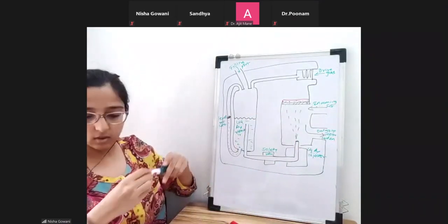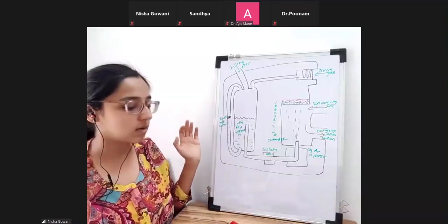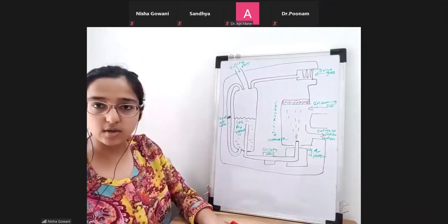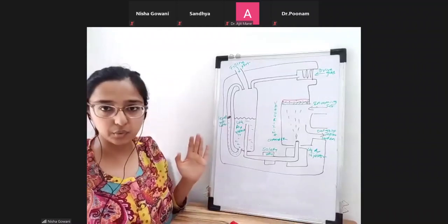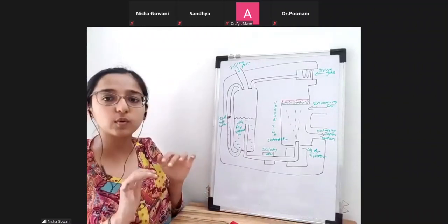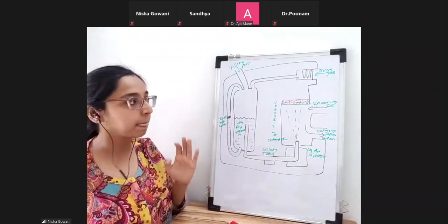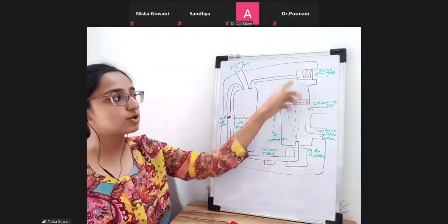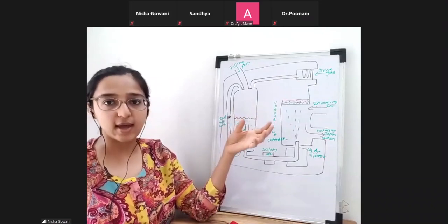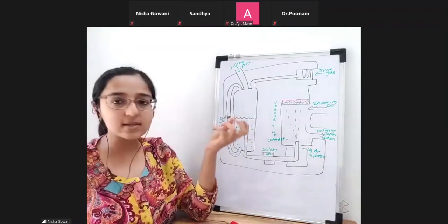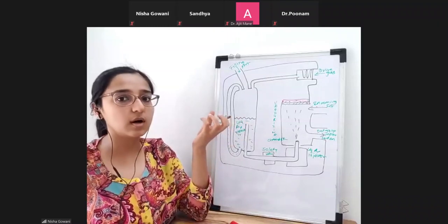So how does this work? I told you that there is no concentration control dial, right? Can you see any concentration control dial? No, there is no concentration control dial. You have to enter into the system how much concentration you want to deliver. Now, there is a driving gas. There's fresh gas, which means oxygen, nitrous. So this gas is used as a drive gas.